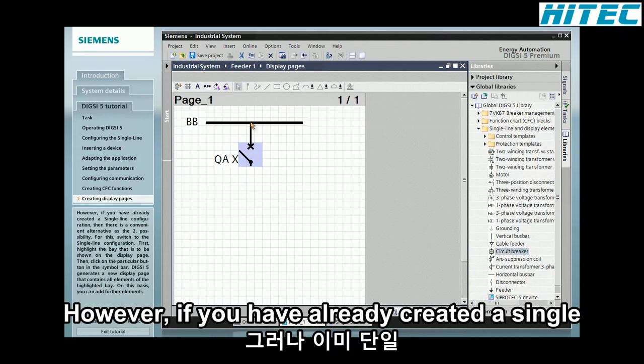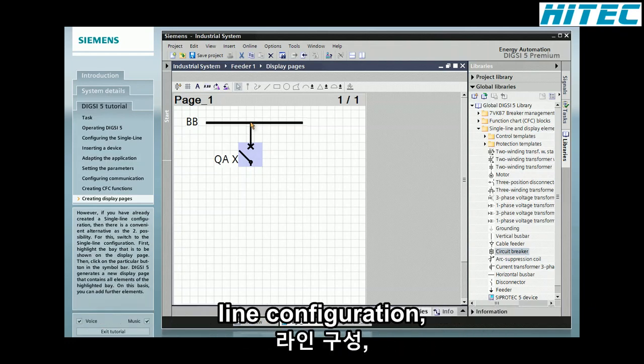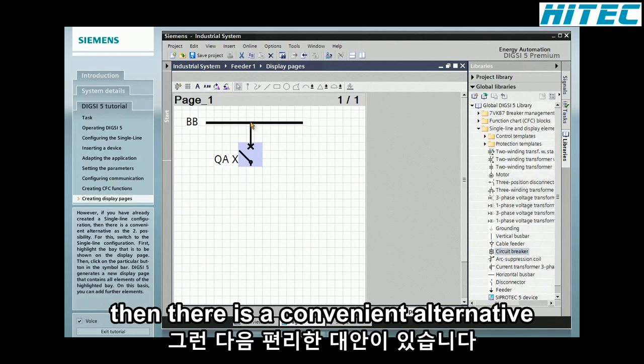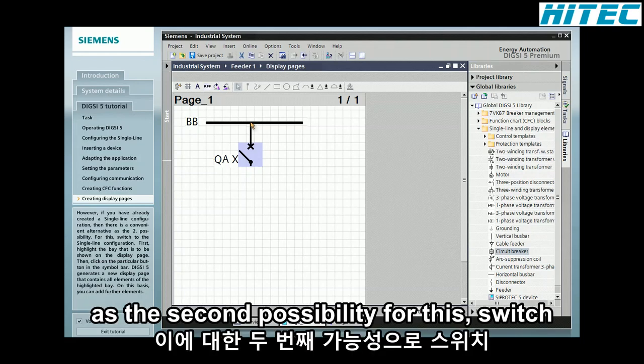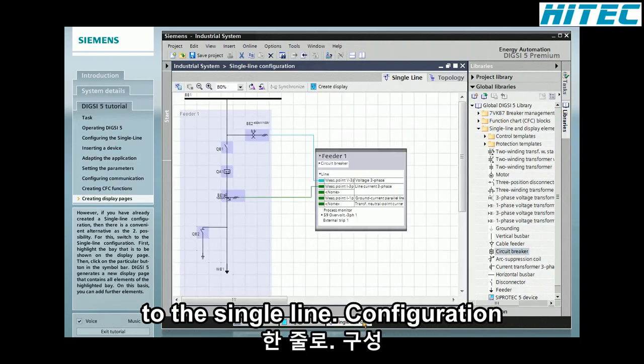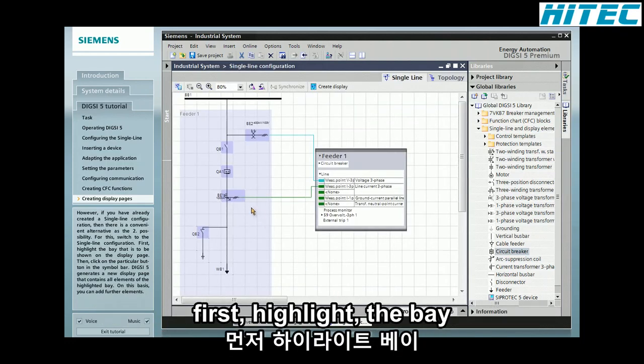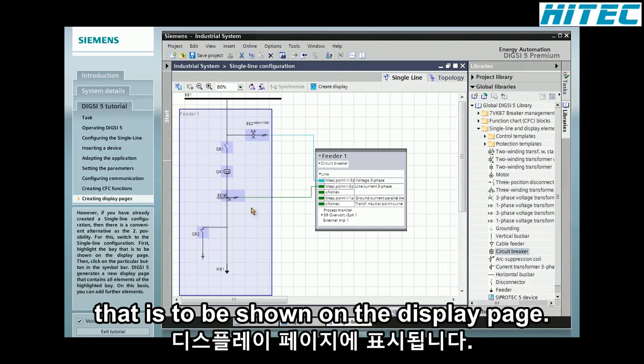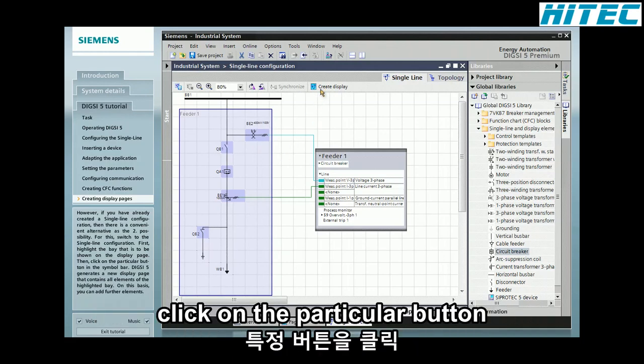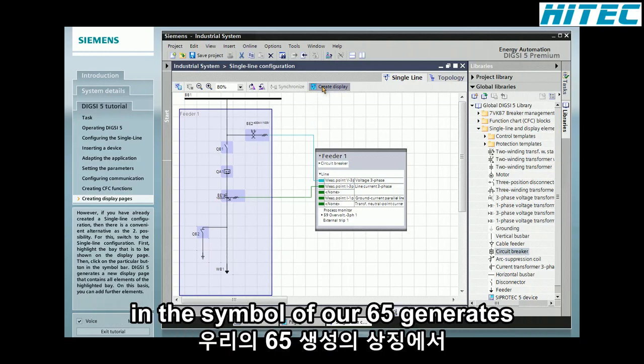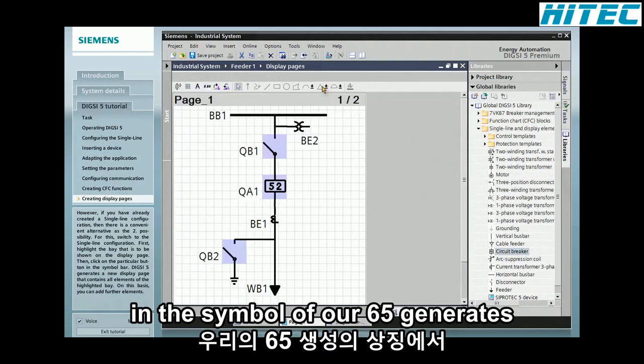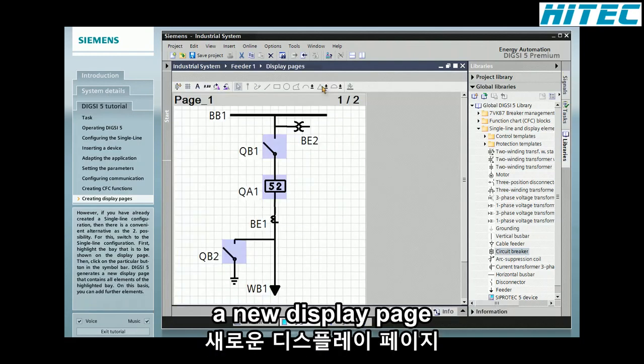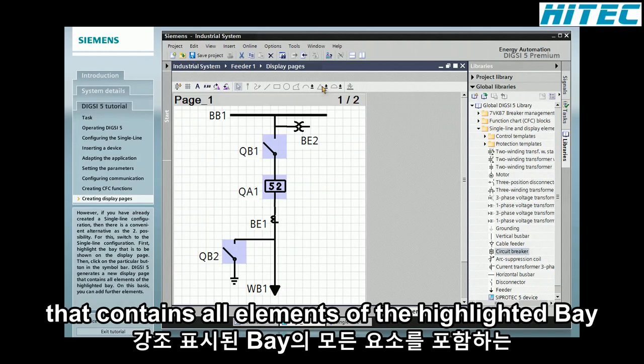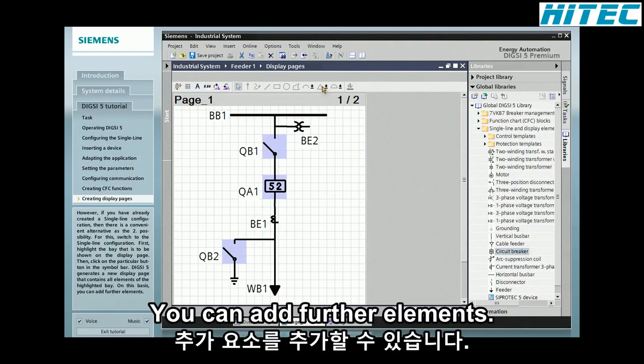However, if you have already created a single-line configuration, then there is a convenient alternative as the second possibility. For this, switch to the single-line configuration. First, highlight the bay that is to be shown on the display page. Then click on the particular button in the symbol bar. DIGSI 5 generates a new display page that contains all elements of the highlighted bay. On this basis, you can add further elements.